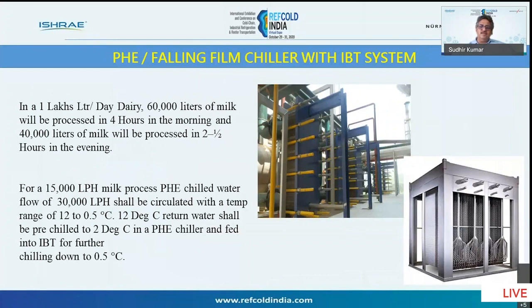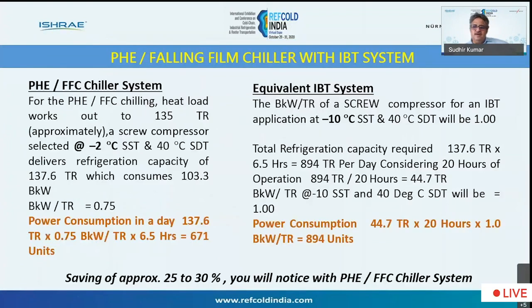So by using this system, you are able to save a lot of power, but definitely there is one disadvantage: you will have a bigger refrigeration plant. So I've made a small comparison. This is an actual comparison which we have made. It's calculated based on the theoretical loads and from the rating charts we have taken.